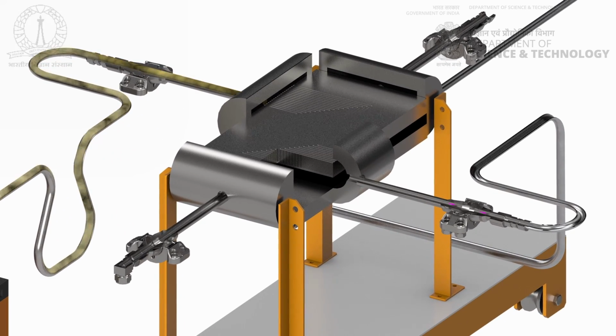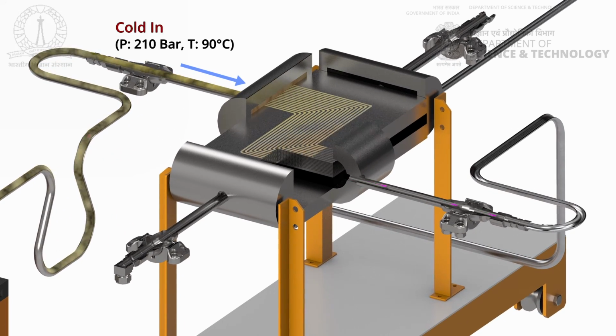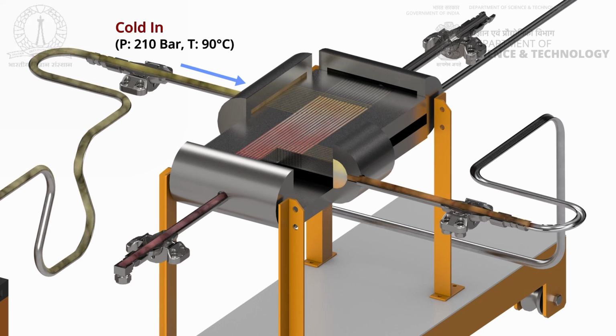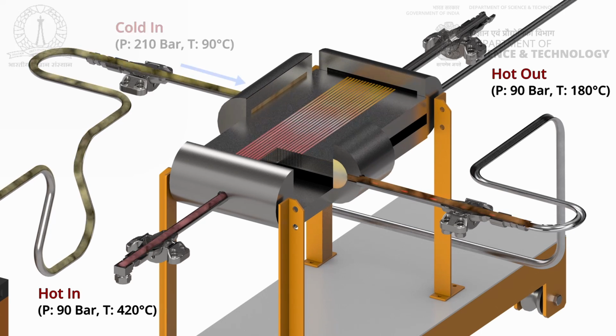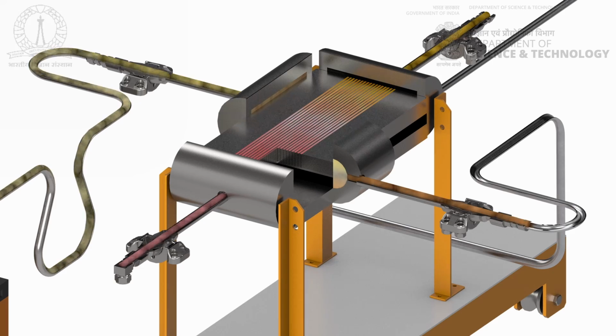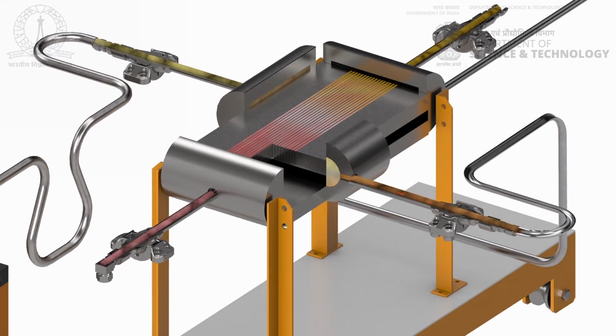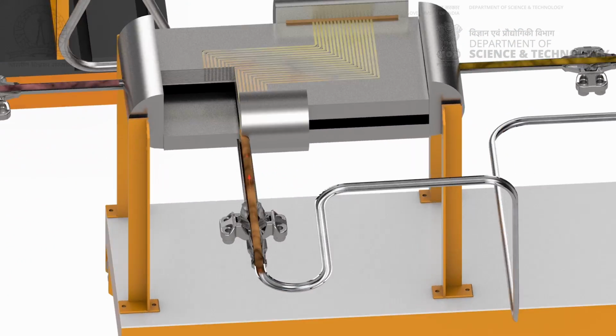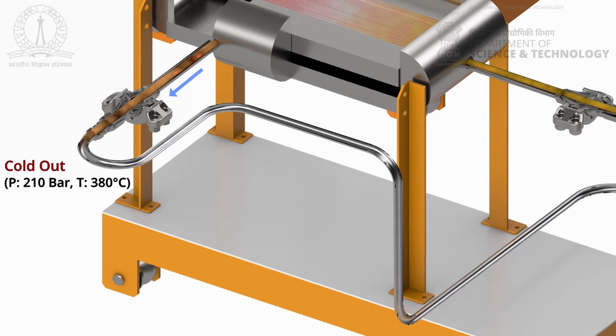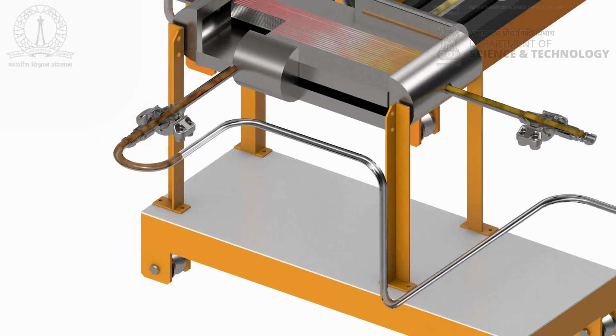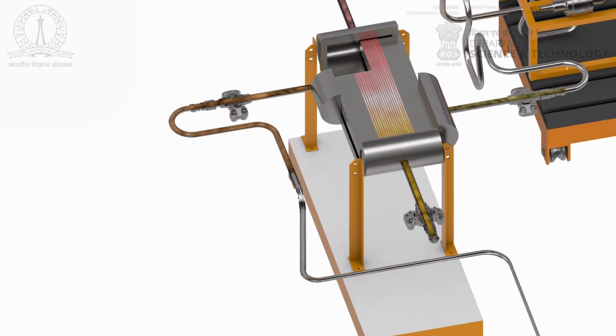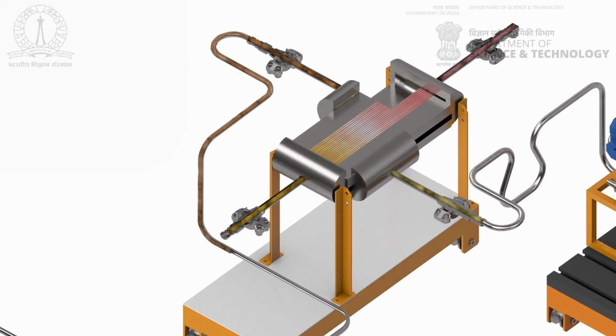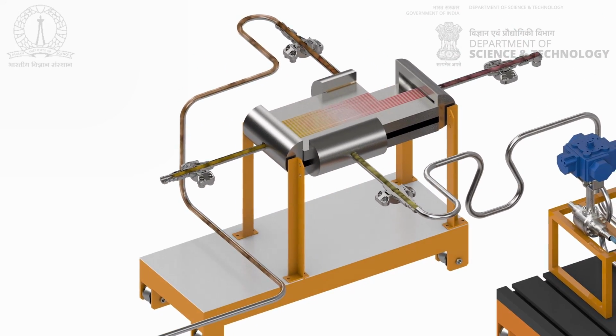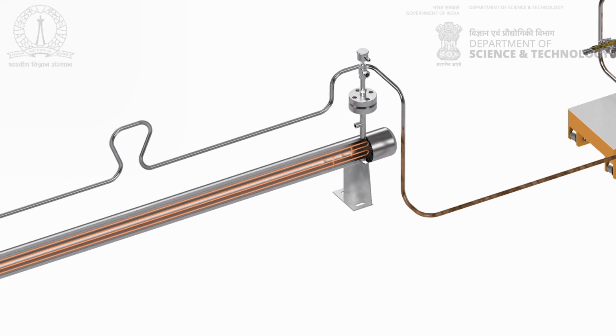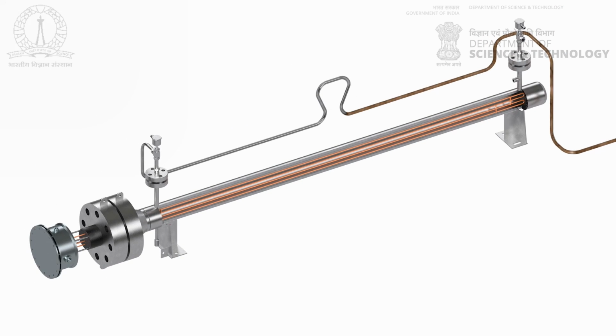Next, the CO2 passes through the recuperator, where it is preheated using residual heat from the turbine exhaust. The two heaters used in the system have different purposes. The first stage heater serves as a replacement for the recuperator during startup when recuperation is absent.